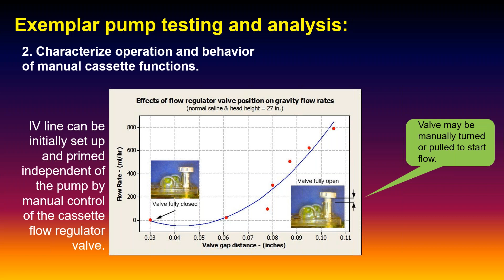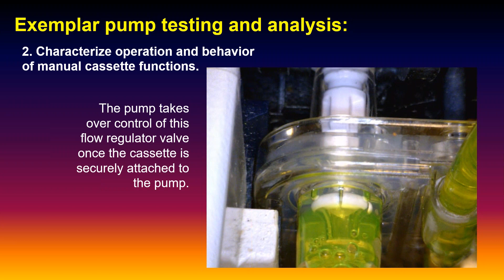And that pump cassette, once it's in the machine, the pump takes over control of the valve. See that? A little pawl comes out now and opens the valve. Now the machine has control over the flow at that point. And when you pull the cassette out, notice the valve got pushed back in. That's how it's designed, that's how it worked.